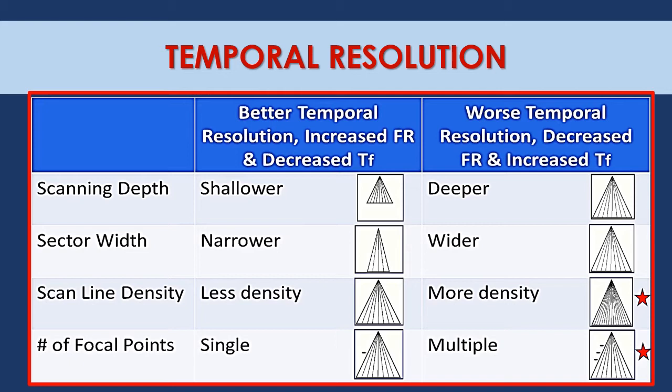So we have here the scanning depth. For scanning depth, if I'm having a shallow scanning depth like here, what will happen? The frame will finish early, so decrease time of the frame. What will happen next? I'll get higher frame rate. I'll get better temporal resolution.